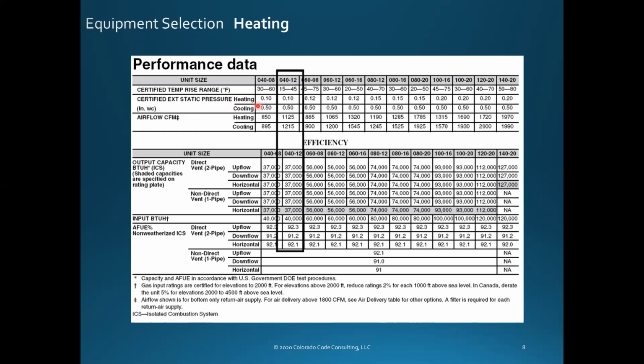They ran it twice. I don't know if I have a screenshot of the fan speed chart, but I'm telling you, the fan speed chart has way more than 2 fan speeds. It's got all the different models starting at a 0.1 external static, and some go to a 0.8 or a 0.9 external static, and they've got CFMs for all 4 speeds. That's just the fan math. So they actually run the test twice and then do math to get all the rest of the speeds, okay?